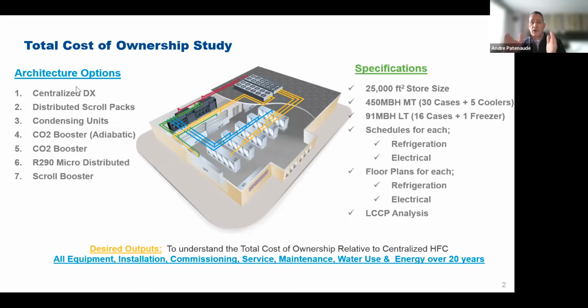So the specifications around the store, when we set the guidelines, we said, let's look at a 25,000 square foot store with 450,000 BTU medium temp, 91,000 BTU low temp. We had about 36 cases in all, 5 walk-in boxes, as you can see there. And we had a design engineering firm actually design all of these stores, these really 8 stores, we're showing 7, as I mentioned, do refrigeration schedules, electrical schedules, floor plans for refrigeration, floor plans for electrical, for all of these stores, so we could cost it out properly.